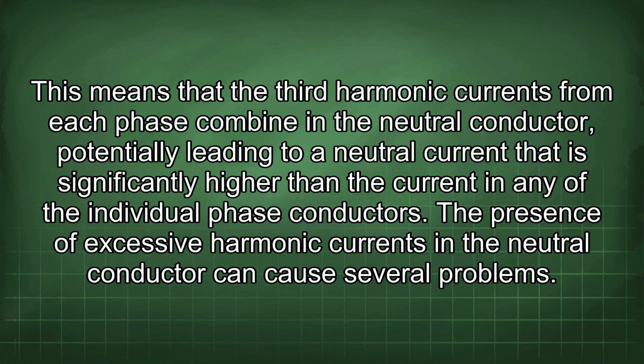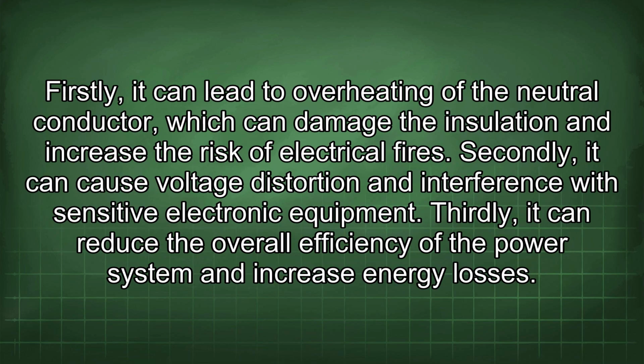The presence of excessive harmonic currents in the neutral conductor can cause several problems. Firstly, it can lead to overheating of the neutral conductor, which can damage the insulation and increase the risk of electrical fires. Secondly, it can cause voltage distortion and interference with sensitive electronic equipment. Thirdly, it can reduce the overall efficiency of the power system and increase energy losses.